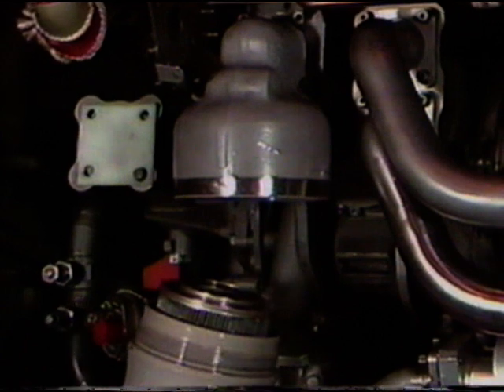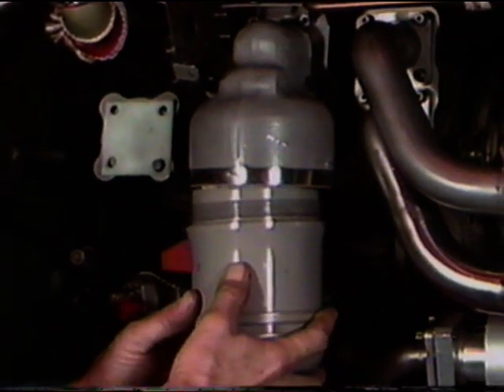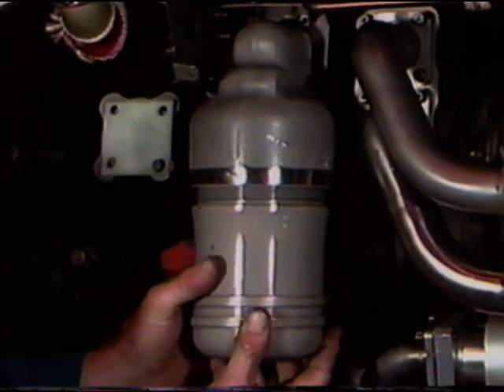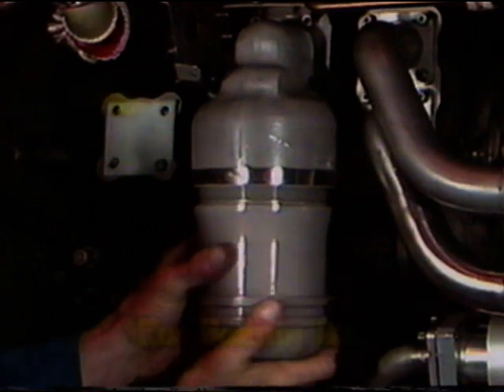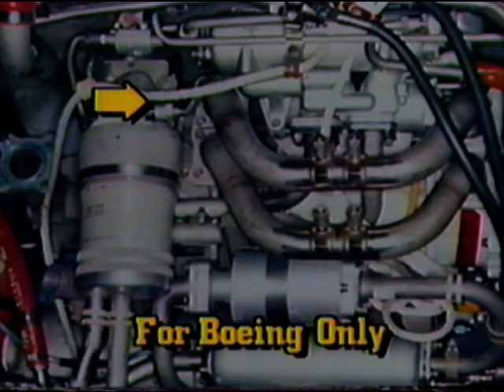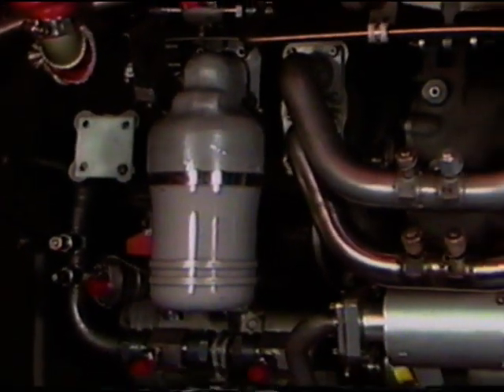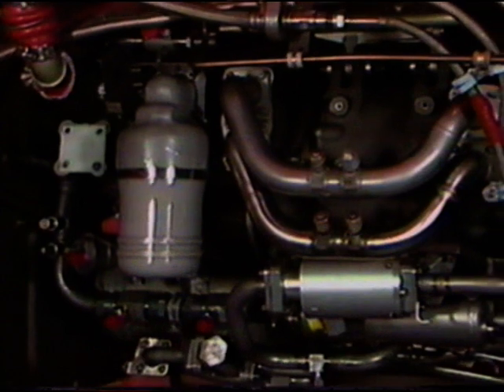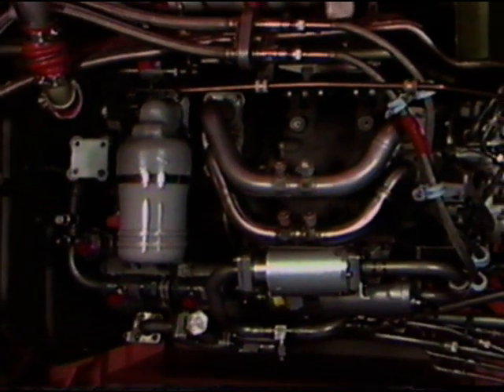If necessary, reinstall the fuel filter bowl. Hand tighten until the bowl flange bottoms against the head. Then connect the fuel line to the fuel filter and the servo heater. Tighten the couplings. After performing the idle leak check and checking the oil level, this will complete the removal and installation of the fuel pump fuel oil heat exchanger.